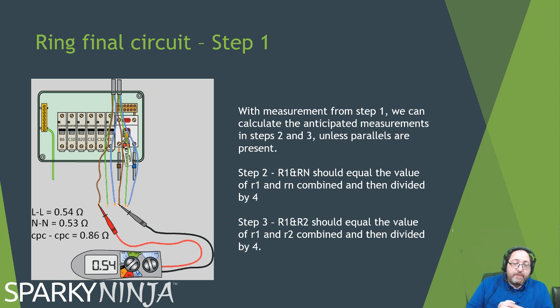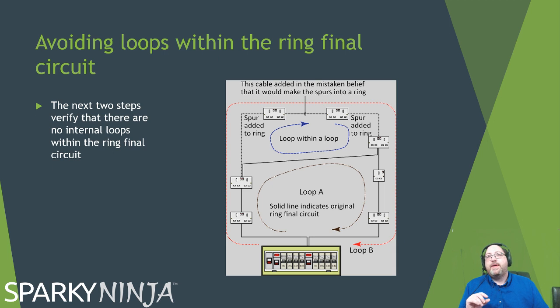Okay, and step 3, we can calculate the line to earth the same way. Now your assessor should give you a lot more time to understand why that is, but to briefly cover it, we want to make sure there are no internal loops. So we measure the end of one line returning to the other. But then to make sure there are no internal loops, we're going to cross connect them. So we're going to take the line of that leg with the neutral of this leg and vice versa.